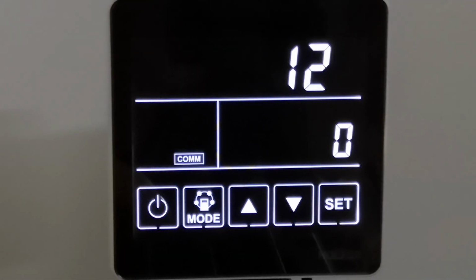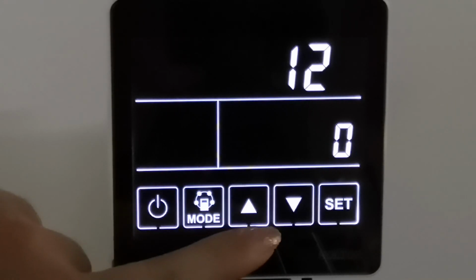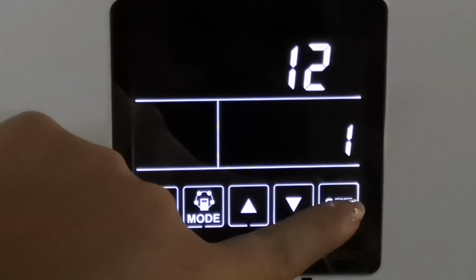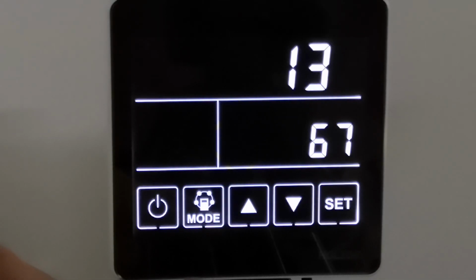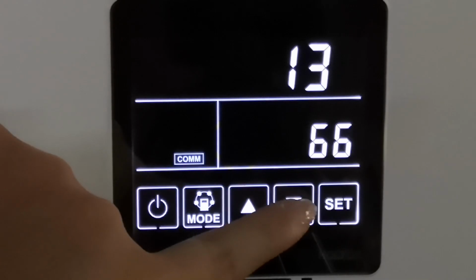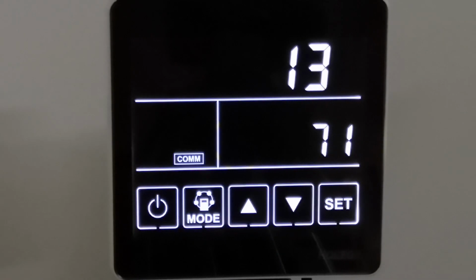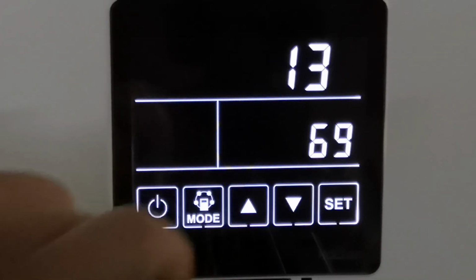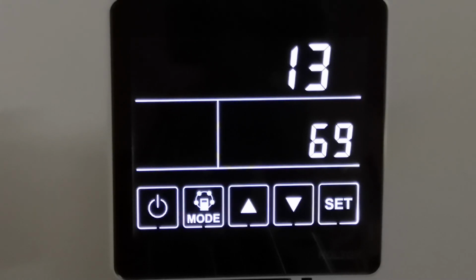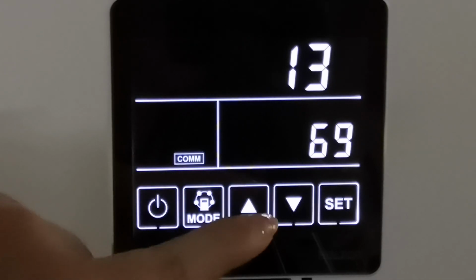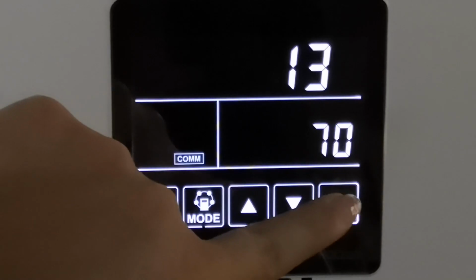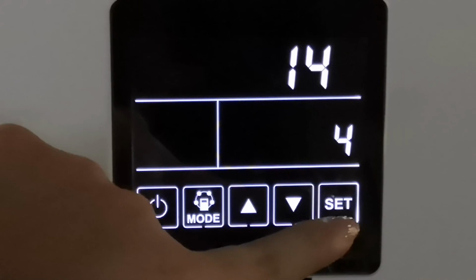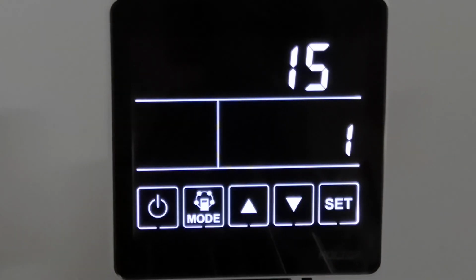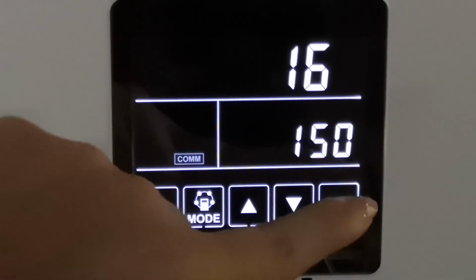Parameter 12 refers to whether the humidity sensor is valid or not. 0 is for invalid. 1 is for valid. Parameter 13 refers to the humidity setting. It is suggested to set the humidity between 60% and 70% when the ventilator is in standby condition or at any speed that is not the highest speed. If the humidity sensor detects that the humidity is higher than the setting value for more than 5 seconds, the ventilator will start up automatically and run at high speed. Only when the humidity is lower than the setting value for more than 5 seconds will the ventilator return to the previous condition. Parameter 14 refers to the IP address, which identifies your ERV. Parameters 15 and 16 are already fixed, unavailable for selection.